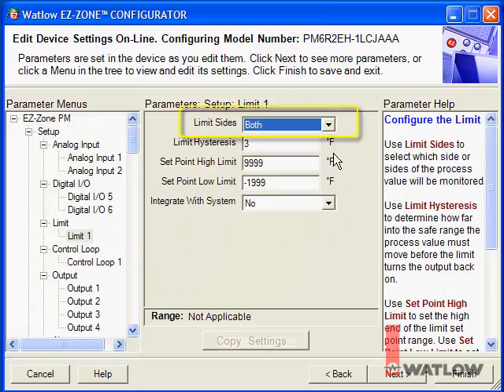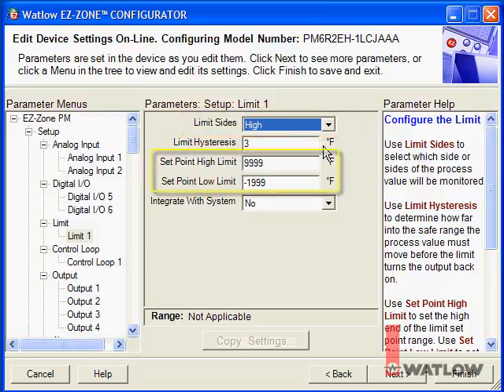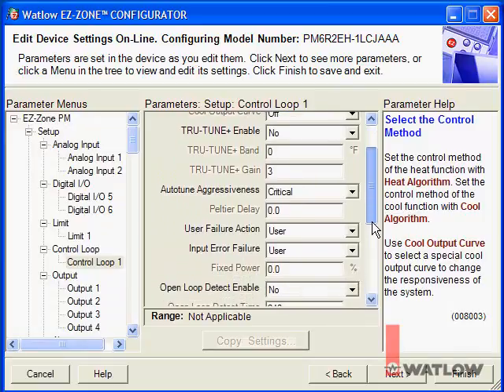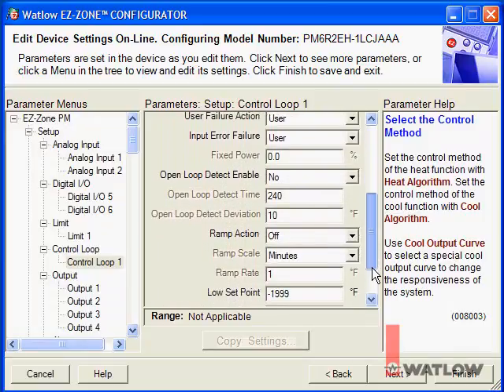Note: the Set Point High Limit and Set Point Low Limit parameters on the Setup Limit menu set the range of values the controller will accept for the limit set points — they are not the limit set points themselves. We'll set the limit set points in a few minutes. Next, let's look at the control loop settings. These are all fine for my application. Now let's consider the outputs.